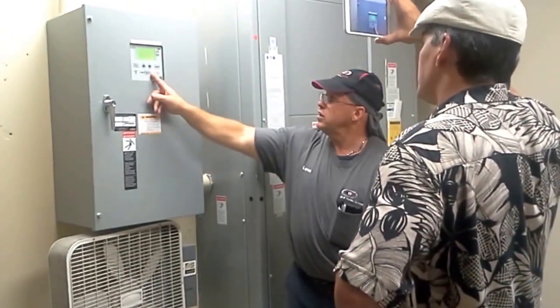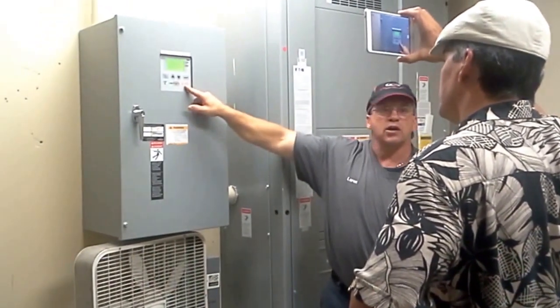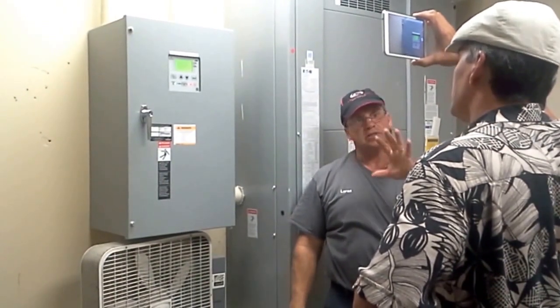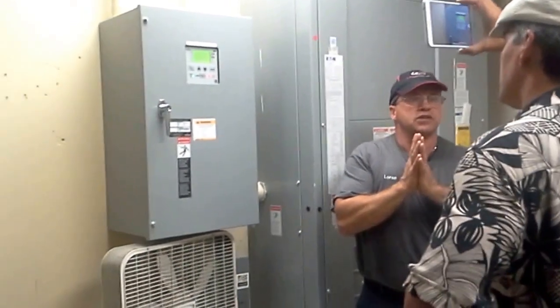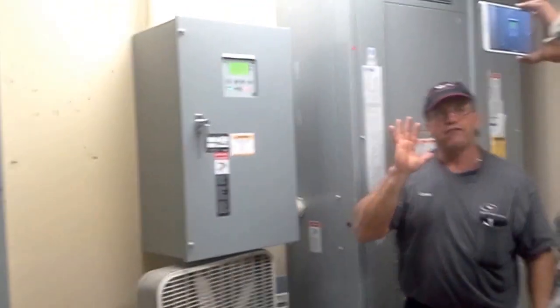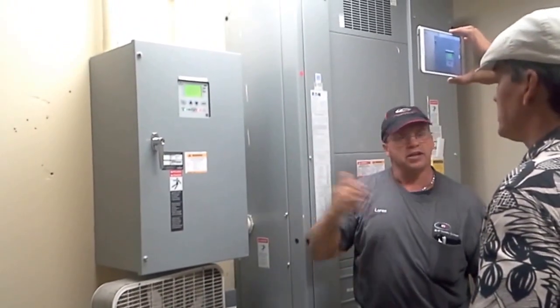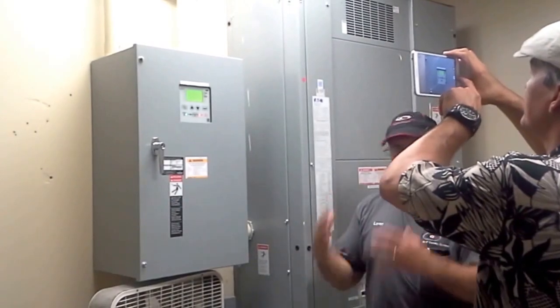It'll switch over. This light will go off. That light will go back on. Then it's going to go down to that 5-minute engine cool down. Remember I said don't hit that emergency stop. You don't want to suddenly hit the emergency stop, right? It would be hot. So it goes to a 5-minute engine cool down. It'll then count down 5 minutes up there. And then it'll turn the generator off. Good. And then it'll be ready for the next time.